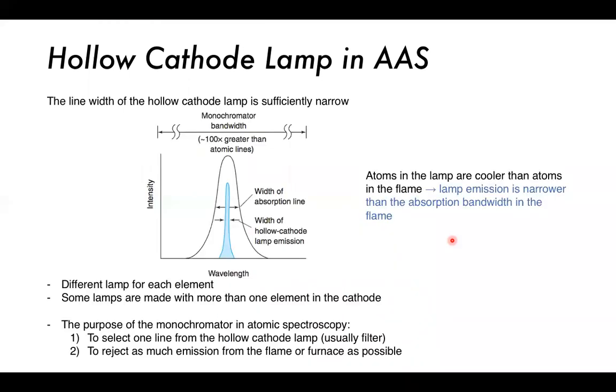The line width of the hollow cathode lamp is sufficiently narrow — usually narrower than what the monochromator can resolve. The blue line represents the width of the hollow cathode lamp emission, while the broader line represents the absorption bandwidth in the flame. Atoms in the lamp are cooler than atoms in the flame, so lamp emission is narrower than the absorption bandwidth due to less Doppler broadening and less collision broadening at lower temperatures.